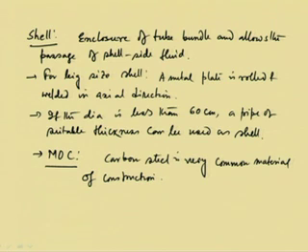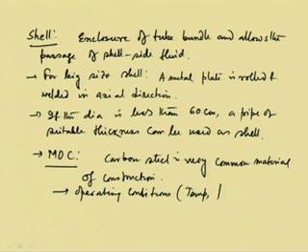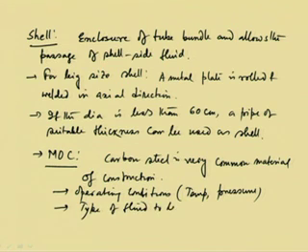Now, this material of construction definitely depends on the operating conditions and also the fluids to be used. Operating conditions means temperature and pressure, these are the main operating conditions. Particularly the temperature is very important, because the fluid reactivity or the corrosion behavior of a fluid on a metal surface depends particularly on the temperature. And then there is the type of fluid to be used. The most important thing is to see that the fluid used for heat exchange, which is passing through the shell side, should not corrode the shell side surface, okay. That is what is of importance. Now, this is the shell.